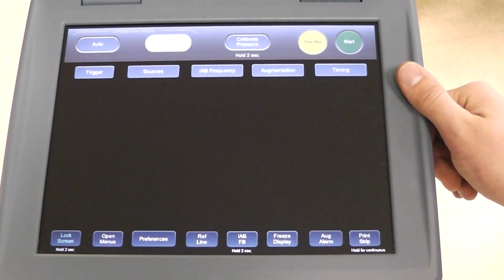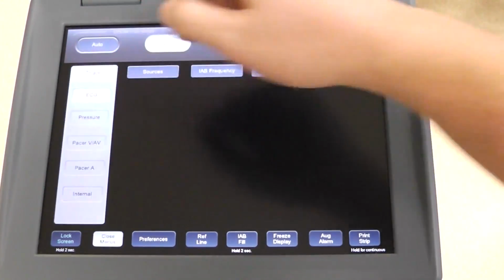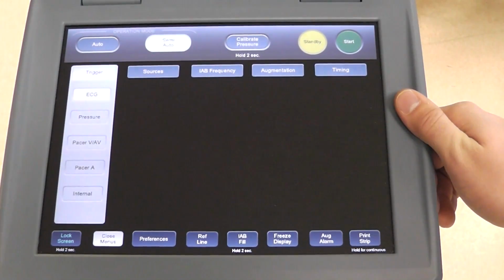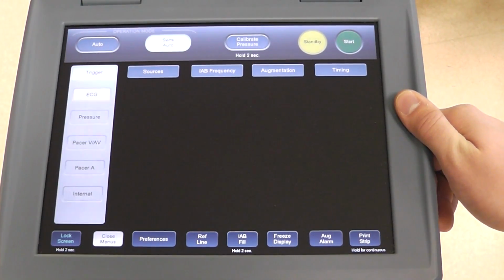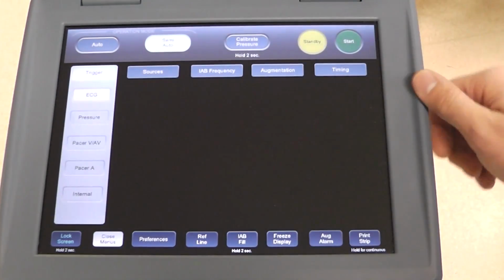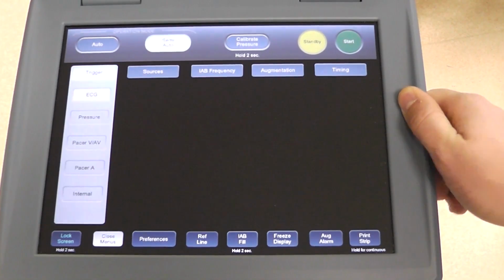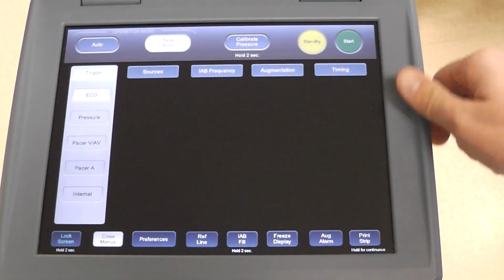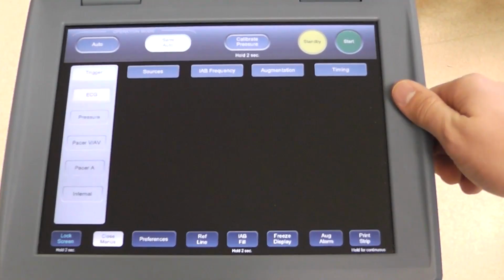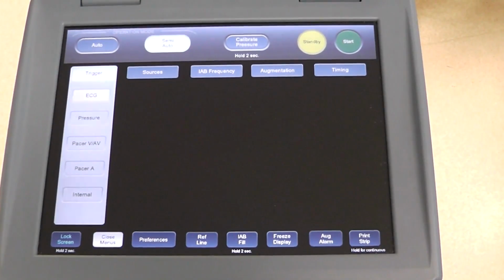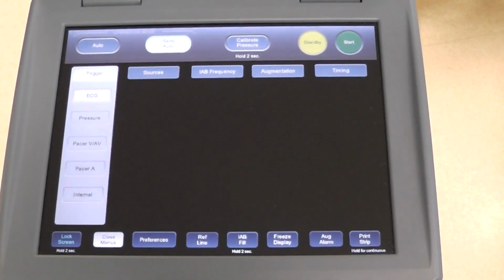So of course, if we want to get out of auto mode, we are going to switch to semi-auto by clicking that. Now we have several different options here. On the far left is trigger. If you select trigger, it will bring up a menu of a whole bunch of different options on what will be the trigger for the balloon to both inflate and deflate. Now by far the most common is ECG. So the balloon will, if it's in auto mode, the software will decide at what point in the ECG it should inflate and at which point it should deflate.